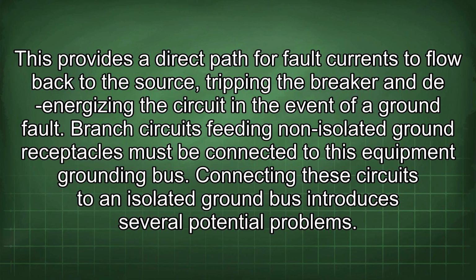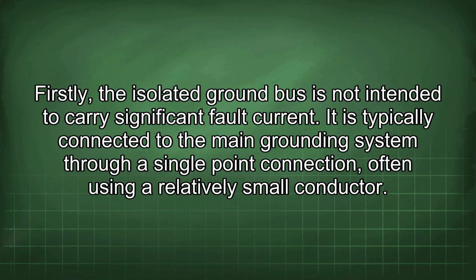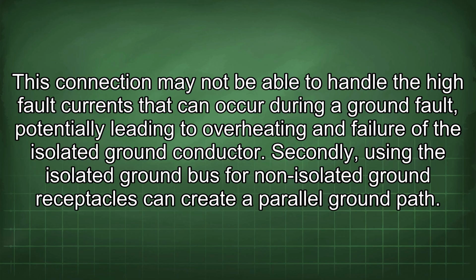Connecting these circuits to an isolated ground bus introduces several potential problems. Firstly, the isolated ground bus is not intended to carry significant fault current. It is typically connected to the main grounding system through a single point connection, often using a relatively small conductor. This connection may not be able to handle the high fault currents that can occur during a ground fault, potentially leading to overheating and failure of the isolated ground conductor.